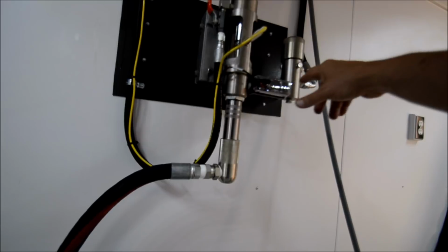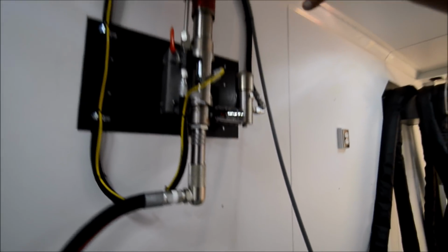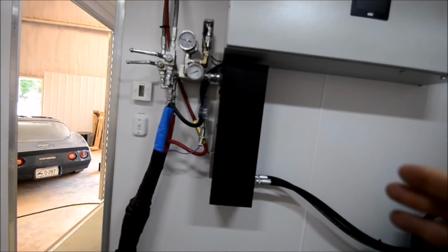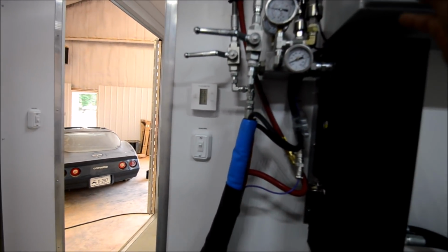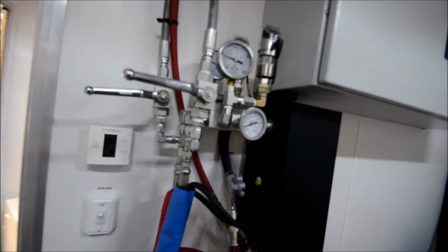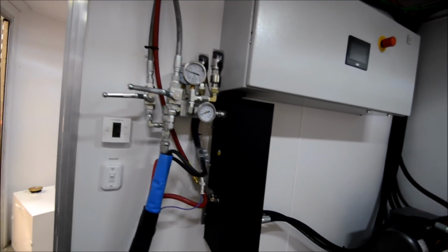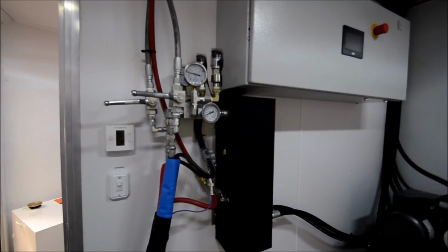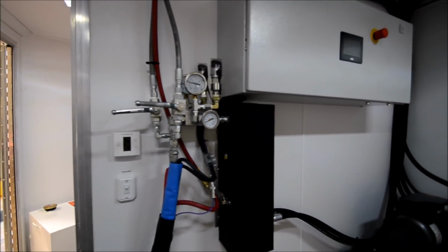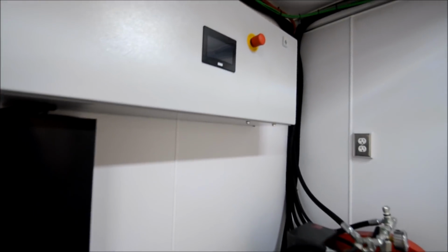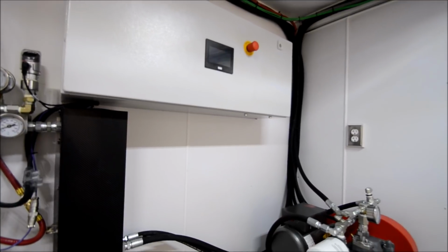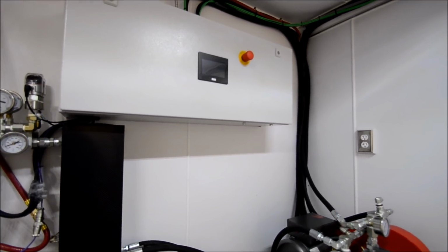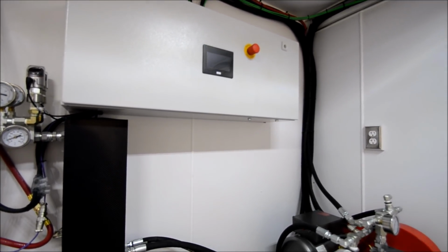It is pressurized. We use these ultrasonic flow meters that keep track of the flow going through the system. Goes into a filter, comes up over the top of the trailer, and comes into our heating system. From our heating system, it goes through this block system here where we have digital pressure gauges as well as analog pressure gauges. So you can get a quick view on what your pressures are on your A and B side and adjust those accordingly. As well, the digital pressure gauges will record in the CPU all of your pressures throughout the day. It will record temperature, it will record strokes, it will record flow using the ultrasonic flow meters.